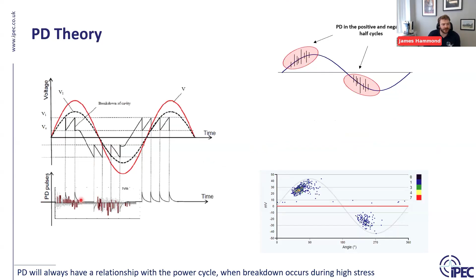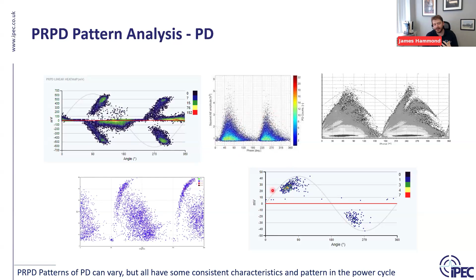These are obviously theoretical, but over here on the right you can see real data, and it lines up quite nicely. So luckily, from the research, it turns out to be quite true. And this is just some examples of patterns. I've brought these up because I've got some examples of PD actually being detected, so you can see what it looks like. Generally you see groupings of these electrical discharges 180 degrees apart, like I say, on those rising and falling edges. You can see that grouping there and there, 180 degrees between them. That's something that was very common in the PD detection world.